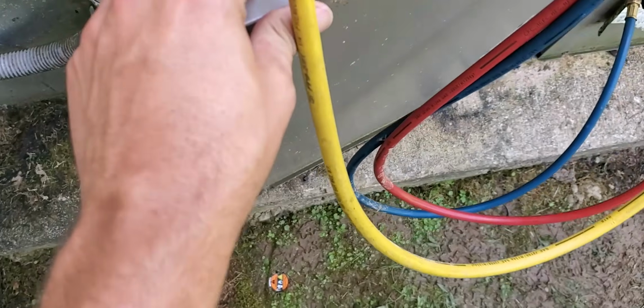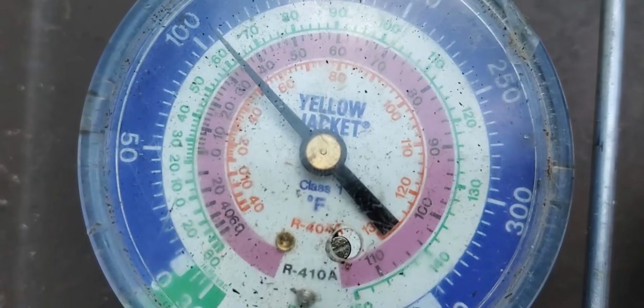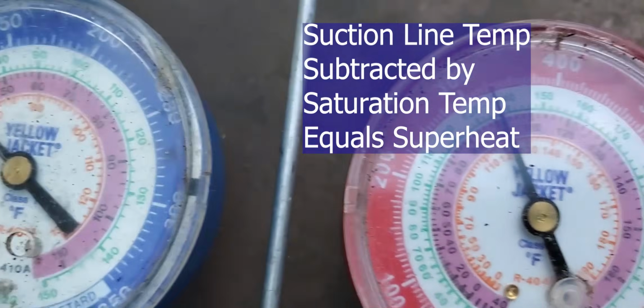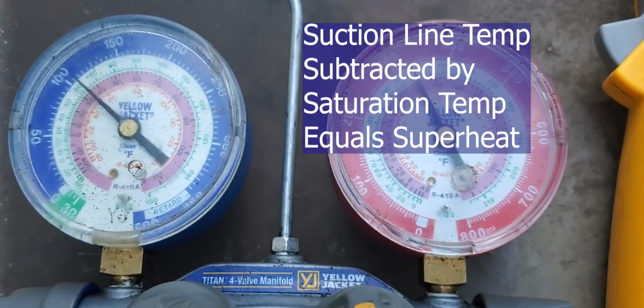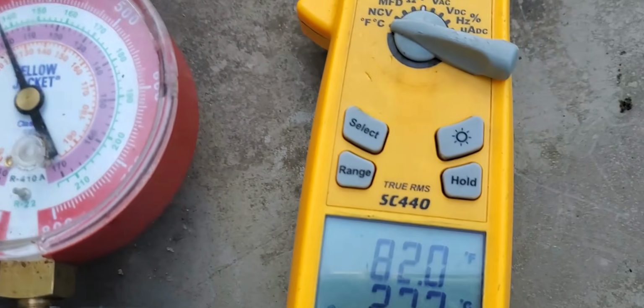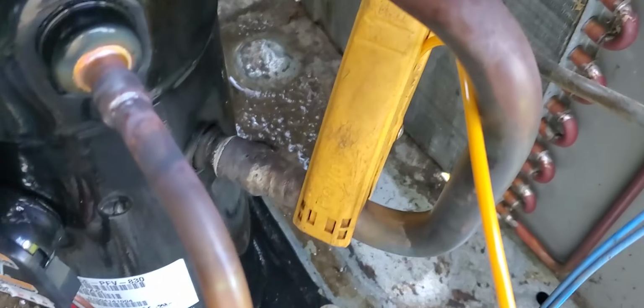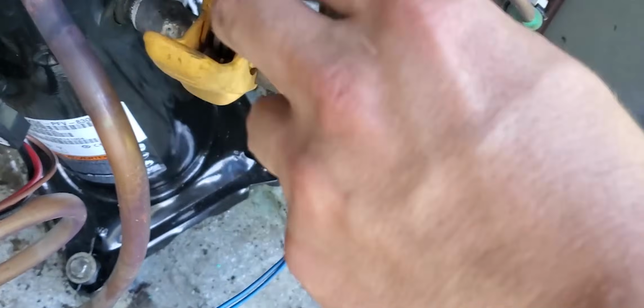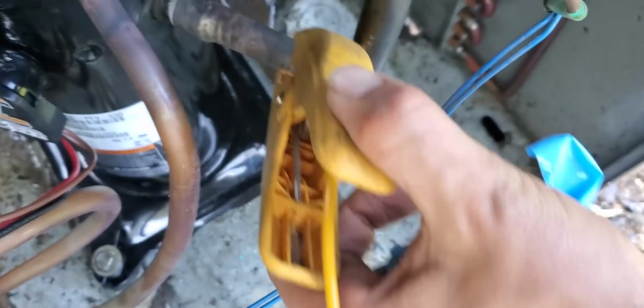After you record the suction line temperature, subtract the evaporator saturation temperature, determined by the pressure measurement, from the temperature of the suction line near the compressor to determine the superheat value. Suction line temperature minus evaporator temperature equals superheat. Compare the calculated superheat value to the target superheat for the measured wet bulb and dry bulb temperatures.